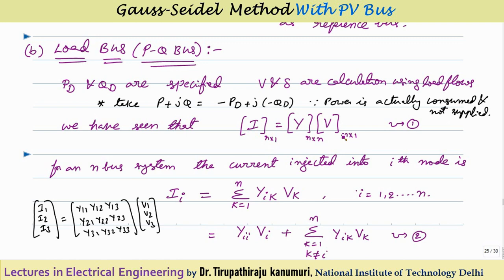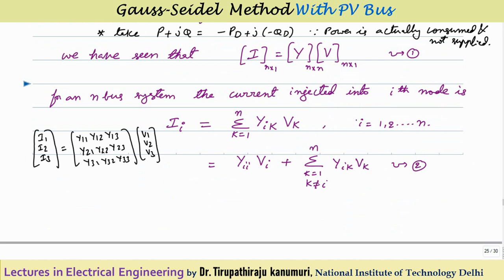Current can be calculated as the admittance matrix multiplied by the voltage matrix. For an N-bus system, the current injected into the ith node - for example in a 3-bus system, I1, I2, I3 - can be represented as Y multiplied by V. To calculate I2: I2 = Y21·V1 + Y22·V2 + Y23·V3. In generalized form, the current injected into the ith bus is Ii = Σ(k=1 to N) Yik·Vk.